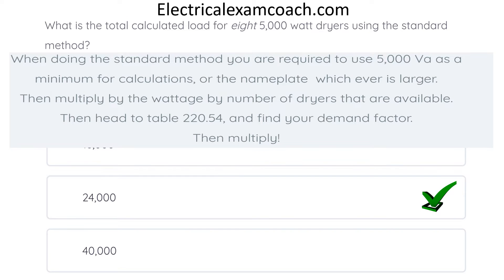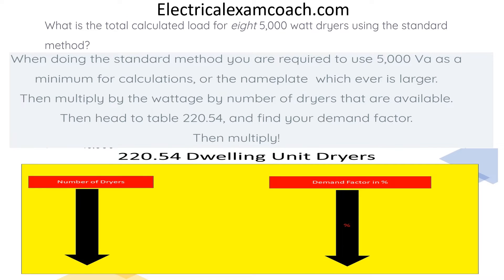When doing standard method calculations, we're required to use 5,000 VAs as a minimum per dryer, or the nameplate, whichever is larger. Then we multiply that individual wattage by the number of dryers we have. Then we head over to table 220.54, find our demand factor, and multiply. When we get to our table, we read the bold heading to make sure we're in the right table — dwelling unit dryers. Then we start on the left-hand side and find our number of dryers, which is 8. Make sure that you use a straight edge on this table so you don't get crossed — use a piece of paper or a pencil.